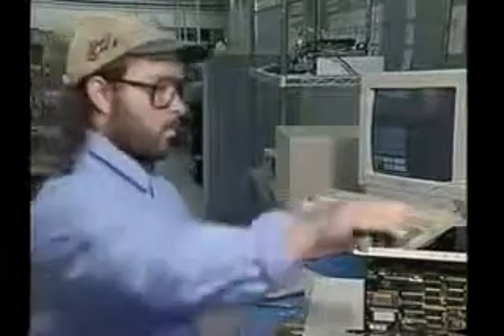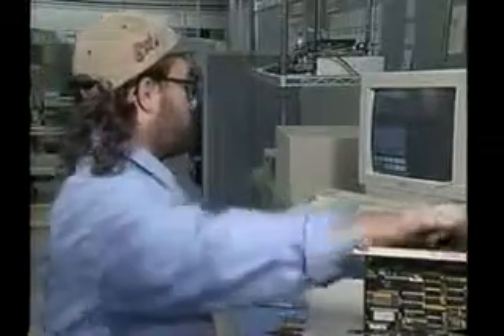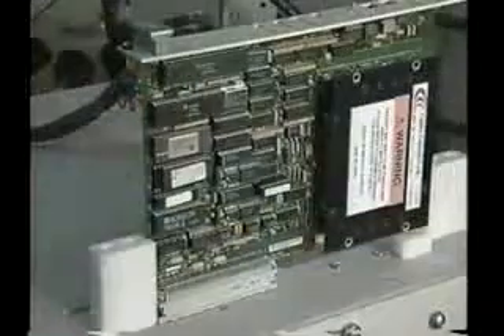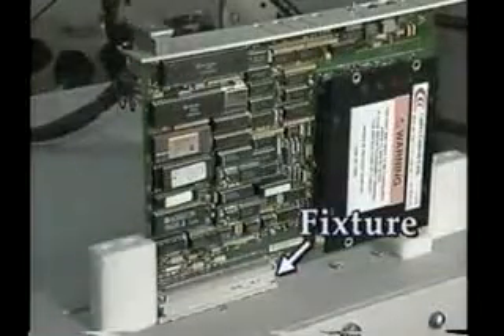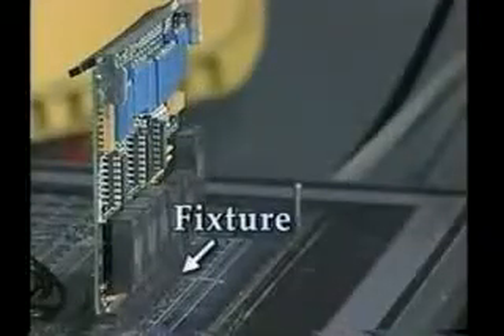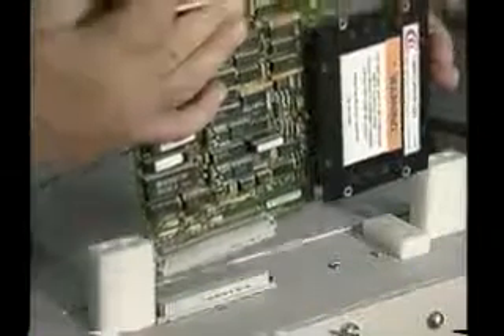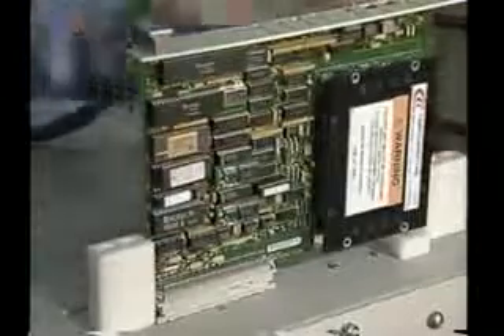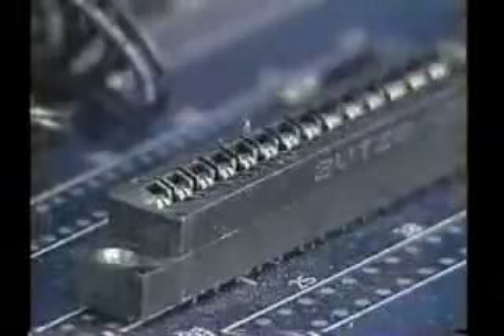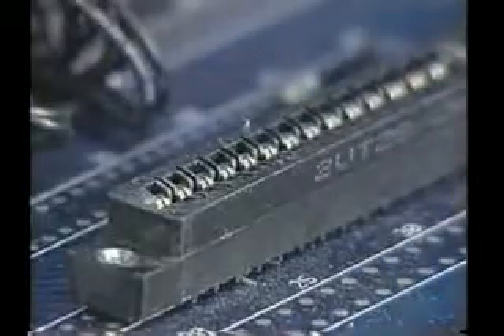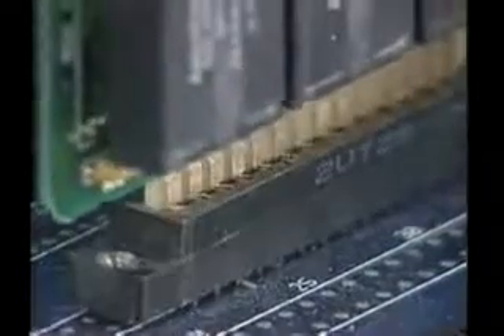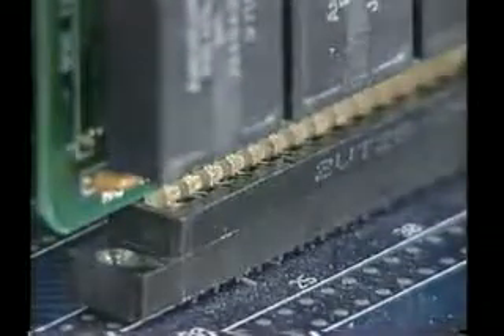Usually, one test station is customized and dedicated to a particular assembly. Unlike ICT, the fixture is hardwired to the tester. Another tester would have a different fixture to interconnect another assembly. There are two different types of fixtures for plugging the assembly into the tester. There may be a test connector that will mate to a connector mounted on the assembly, or an edge-type connector. This connector allows the assembly to be plugged in directly, just like it would be connected in the chassis of the finished product.